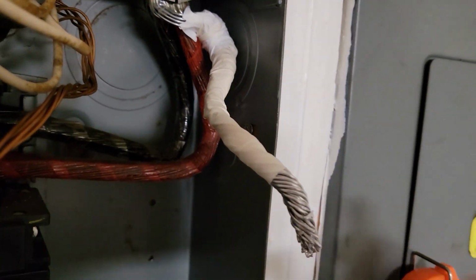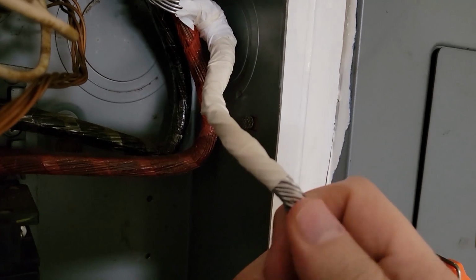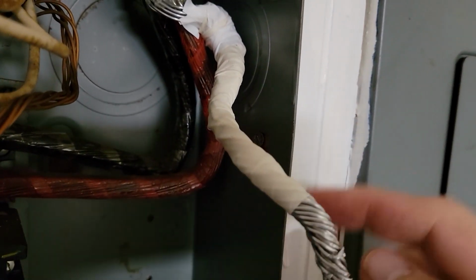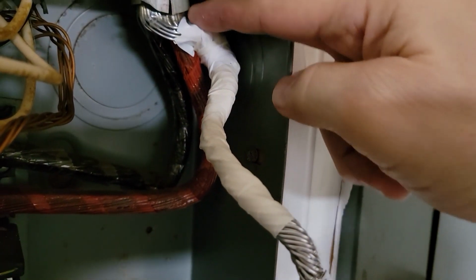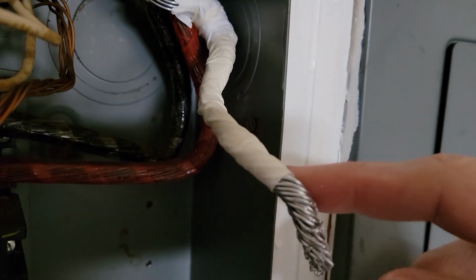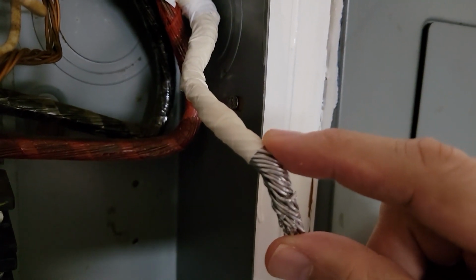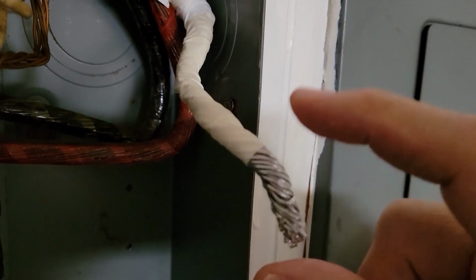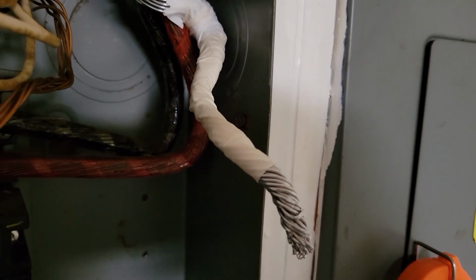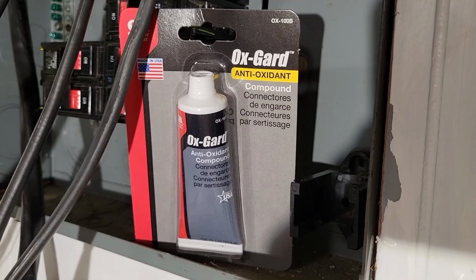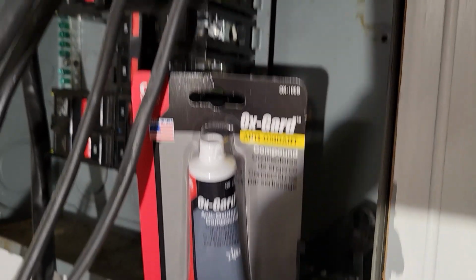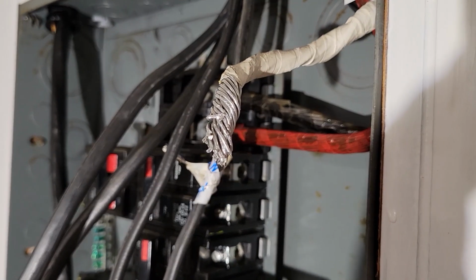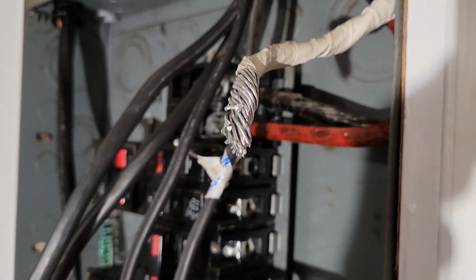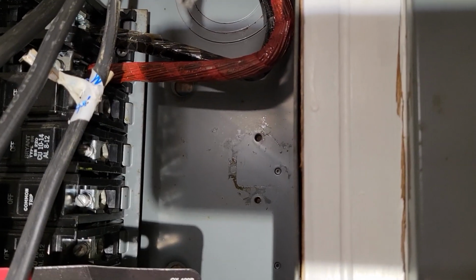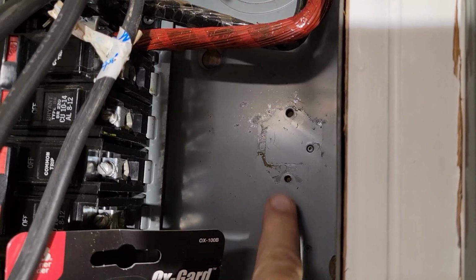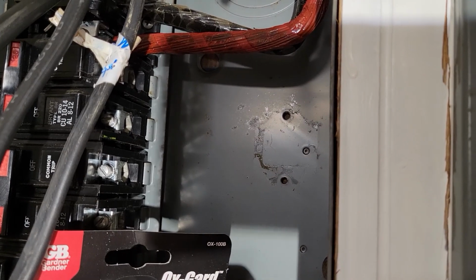We use the pliers to just wind this up a little bit so that it's nice and tight, and then just cover it from as far back as we could, leaving about an inch or so of the tip exposed so that it can be mounted on the neutral lug. Here's the antioxidant compound that we're going to be applying to the end of the neutral cable, which then will connect to the neutral bar that'll go where this marking is right here.